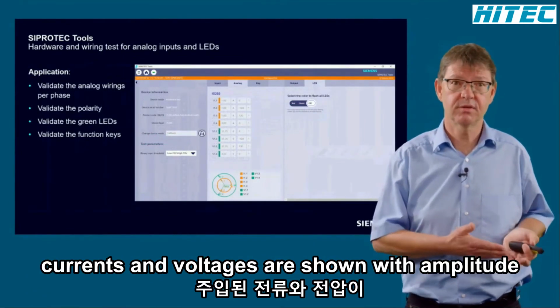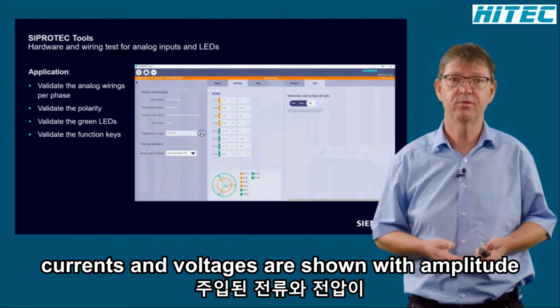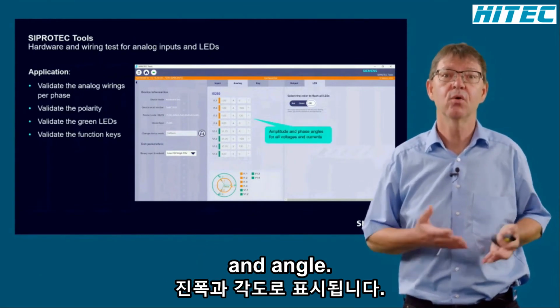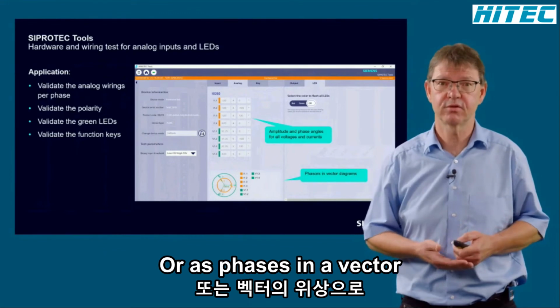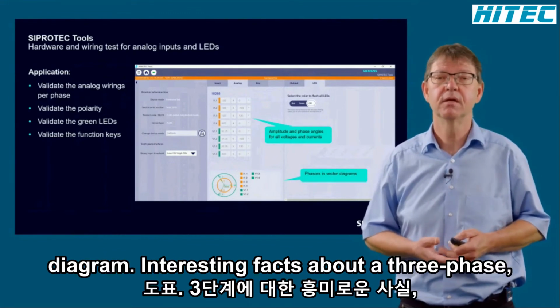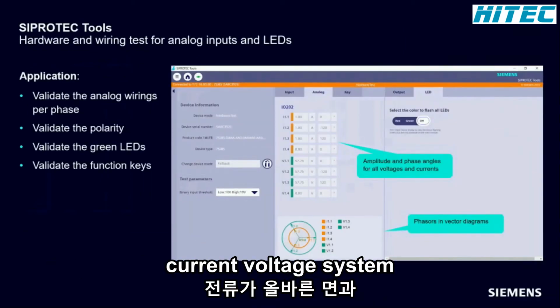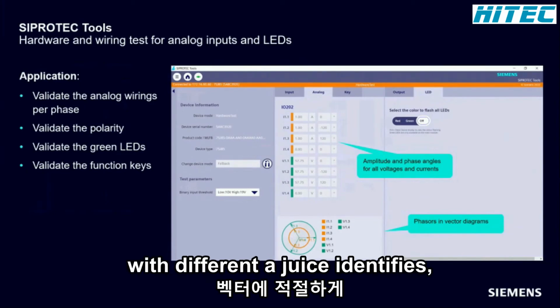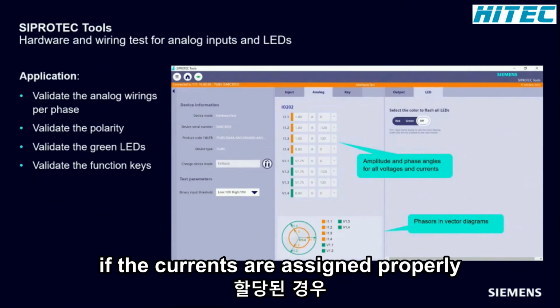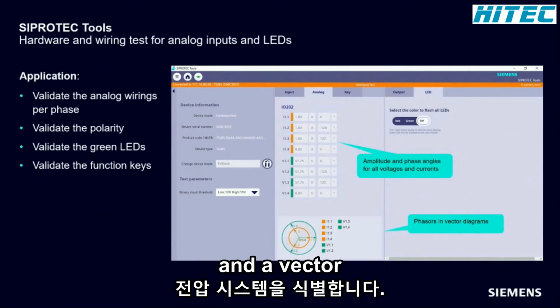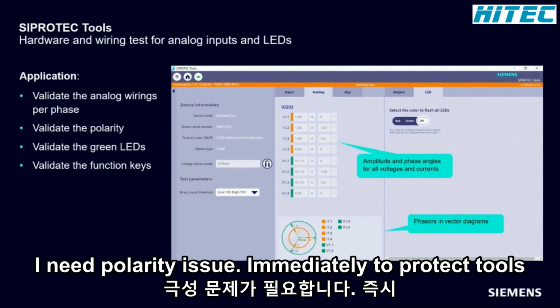Also, injected currents and voltages are shown with amplitude and angle, or as phasors in a vector diagram. Injecting, for example, a three-phase current or voltage system with different amplitudes identifies if the currents are assigned properly to the correct phases, and the vector diagram reveals any polarity issue immediately.